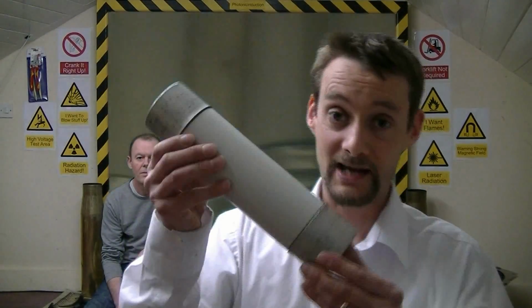Right guys, as promised, video on these 11 kV fuses. These have come out of substations, and we've got rather a quantity of them. They've all been upgraded because we're all using a little bit too much electricity these days, and the primary fuses on the 11 kV transformers need to be a little bit bigger than this. I think this one's only 36 amps, but 36 amps at 7 kV or 11 kV is quite a bit of grunt. So we're going to have a look at these, blow them up, and do whatever's necessary, and have a look in detail.